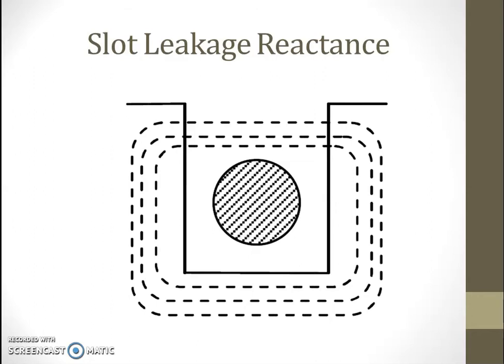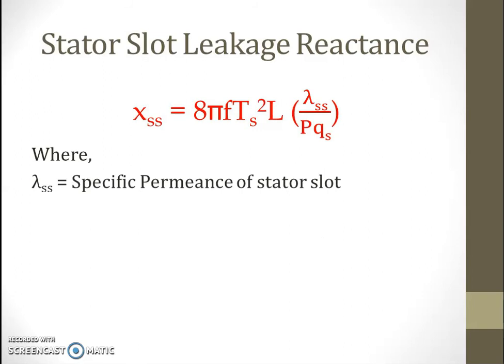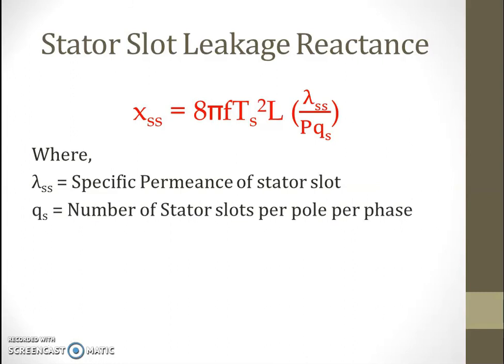We cannot completely eliminate leakage flux in a three-phase induction motor, so during design we must calculate these leakage fluxes appropriately and derive leakage reactance from them. Starting with slot leakage reactance: stator slot leakage reactance Xss is given by 8·pi·f·Ts²·L·lambda_ss / (p·qs), where f is frequency, Ts is stator turns per phase, L is stator core length, lambda_ss is specific permeance of stator slot, and qs is number of stator slots per pole per phase.